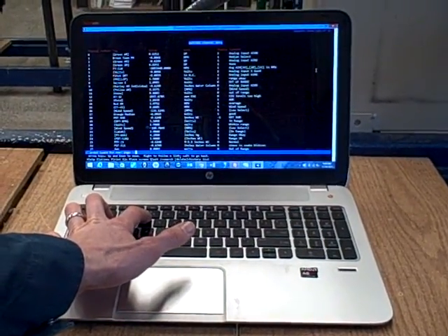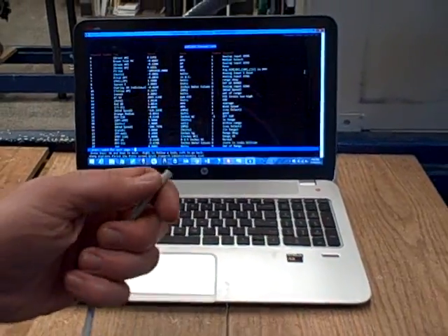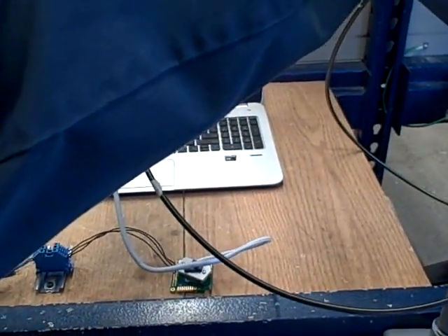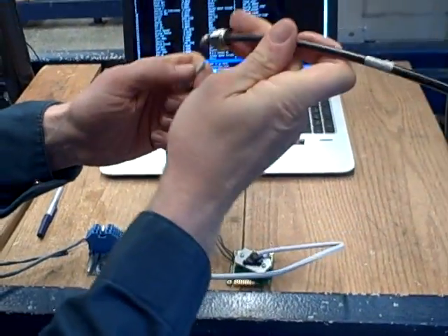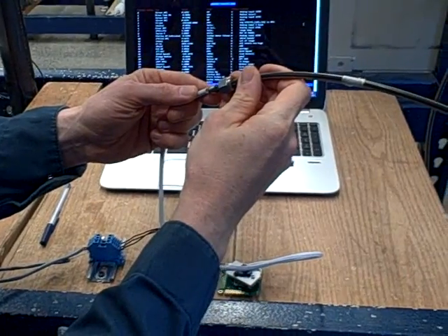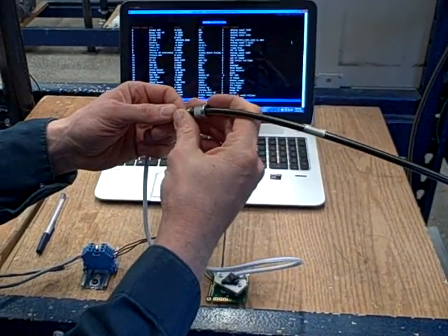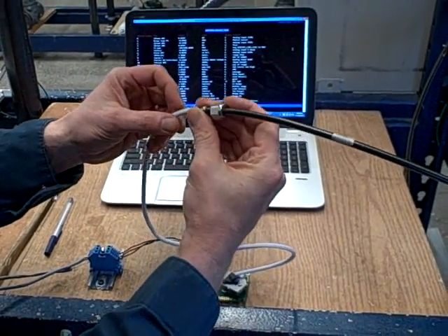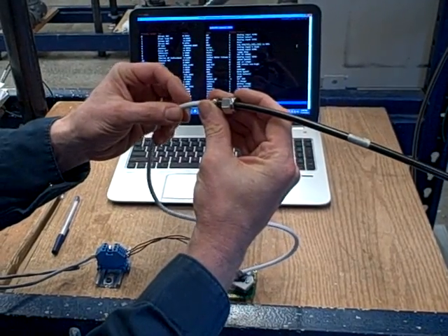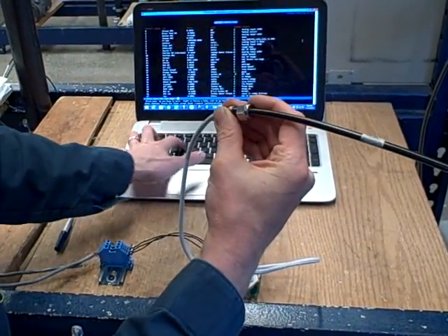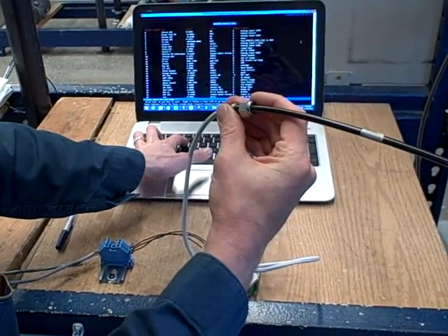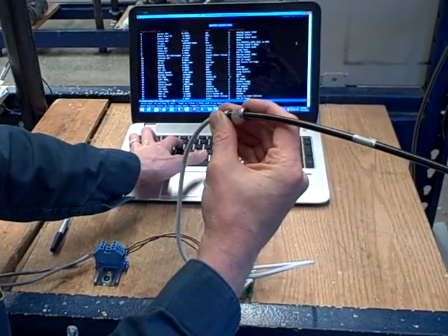We're still saturated high. To get this down, I'm going to turn on a source of compressed air. We've got a very small amount of compressed air coming out of here. I'll just play that stream of compressed air into the end of the sample tube. I'll keep a bit of an air gap there so I don't build up any significant pressure inside the sensor. And I'll refresh the SCADA system.